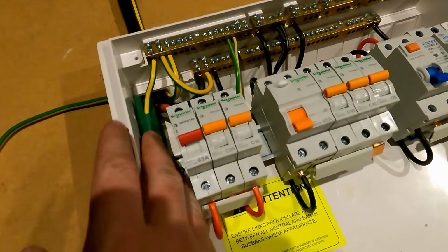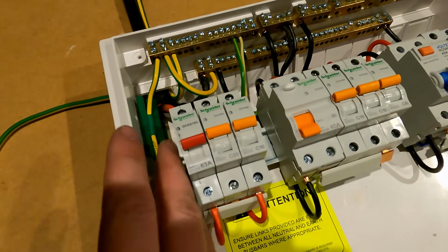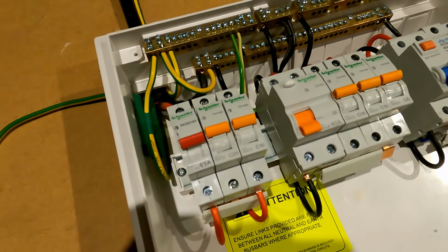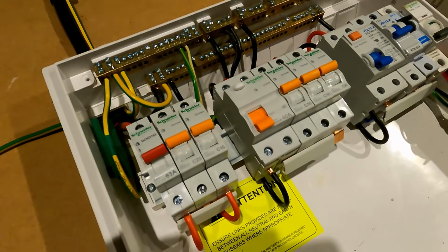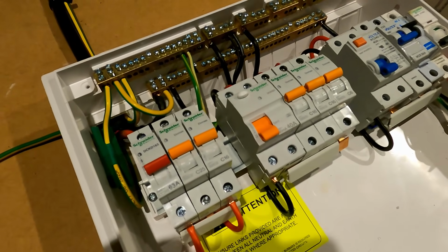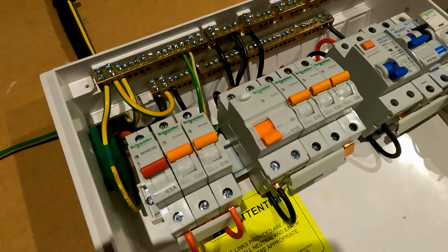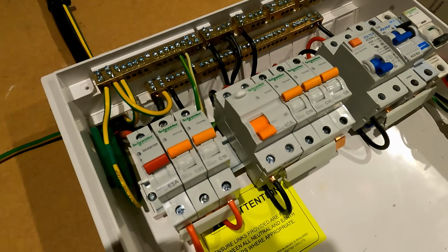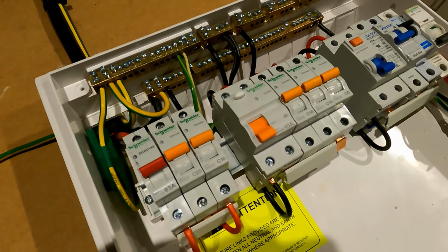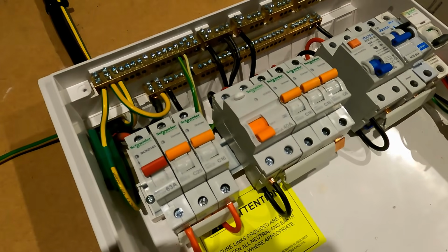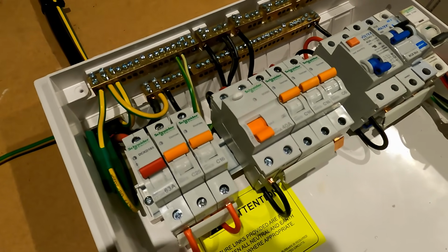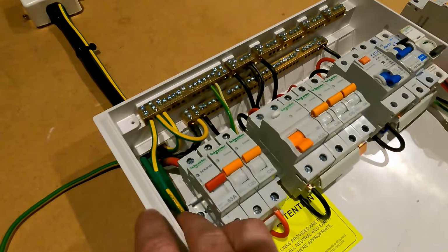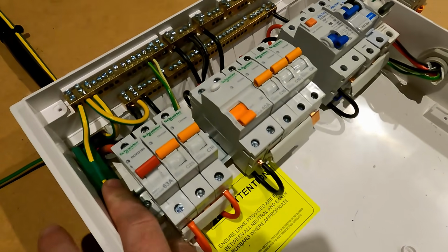So the next thing is the main earth label here. I believe that everyone should be putting them on switchboards. You always get a sparky out there who says it's not required or it's not legislation, but it's just the same as saying putting a socket on the wall, that it's not legislation to make sure they're level. Don't be lazy, just throw them on. They actually come with the switchboard as well.